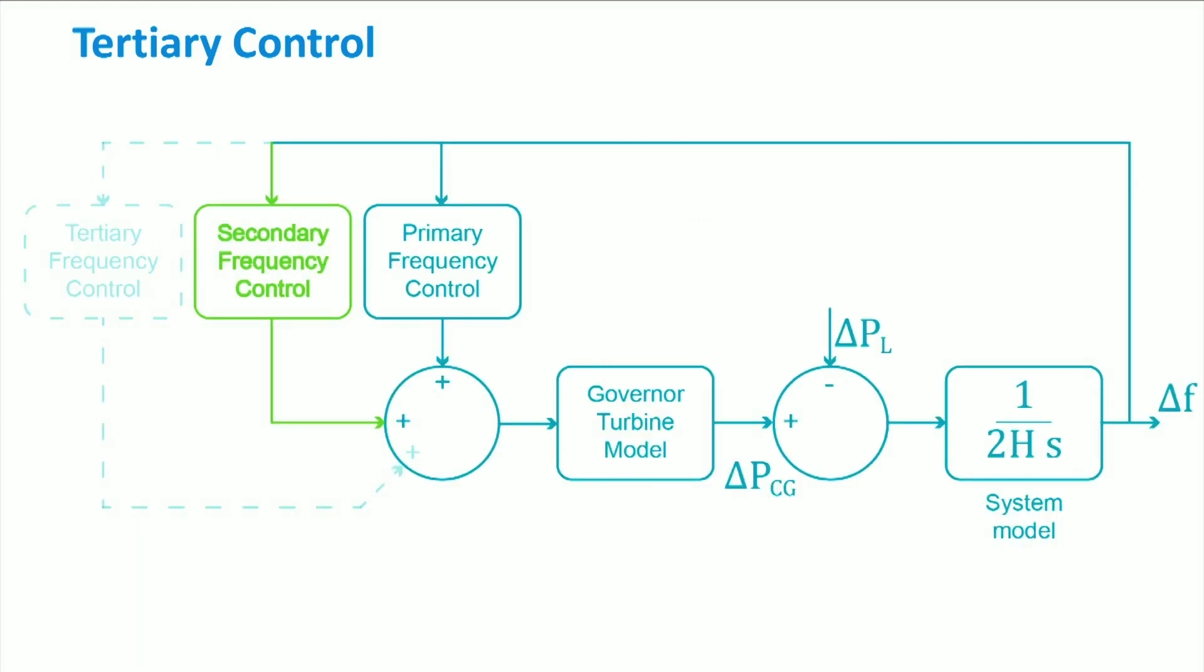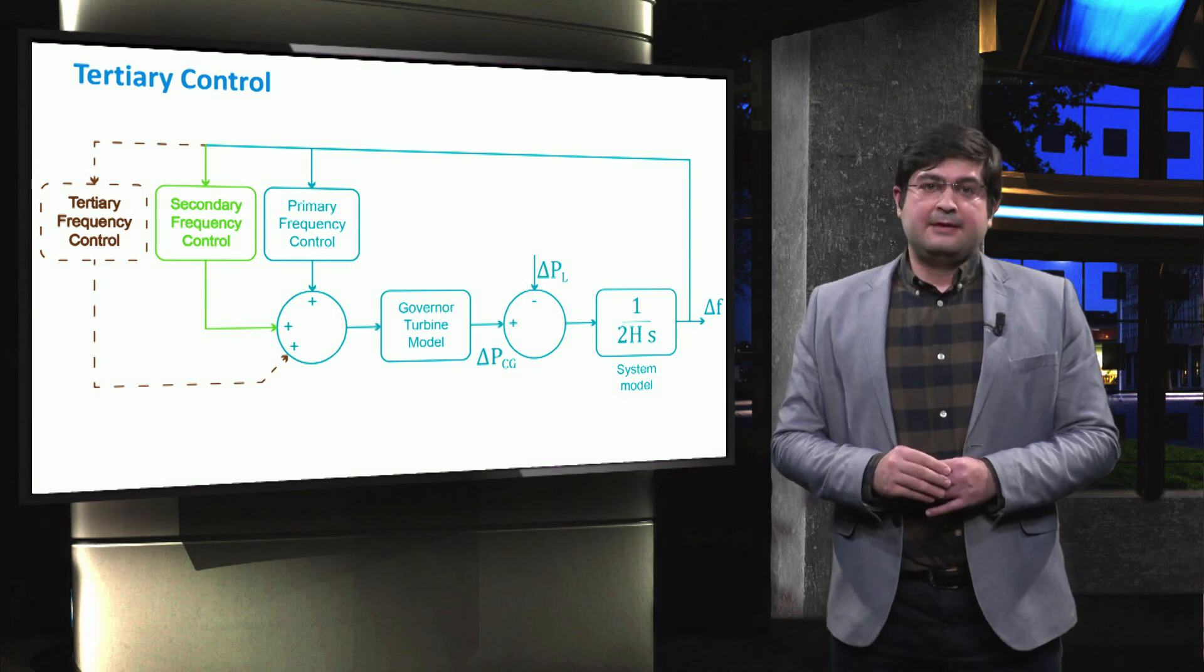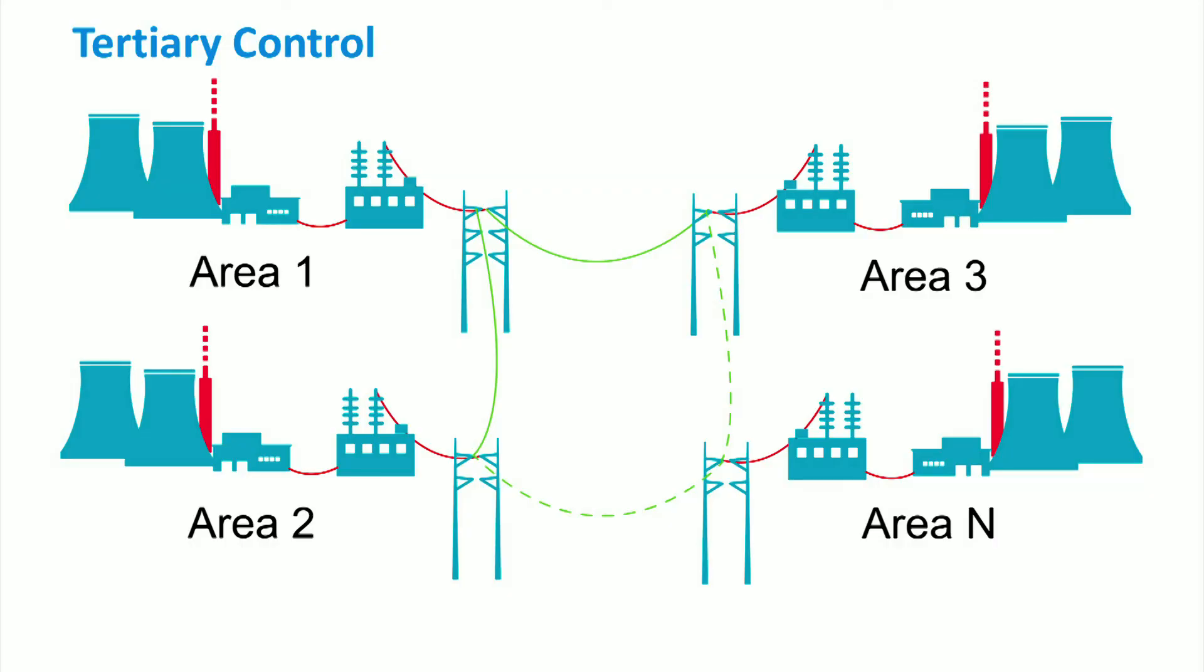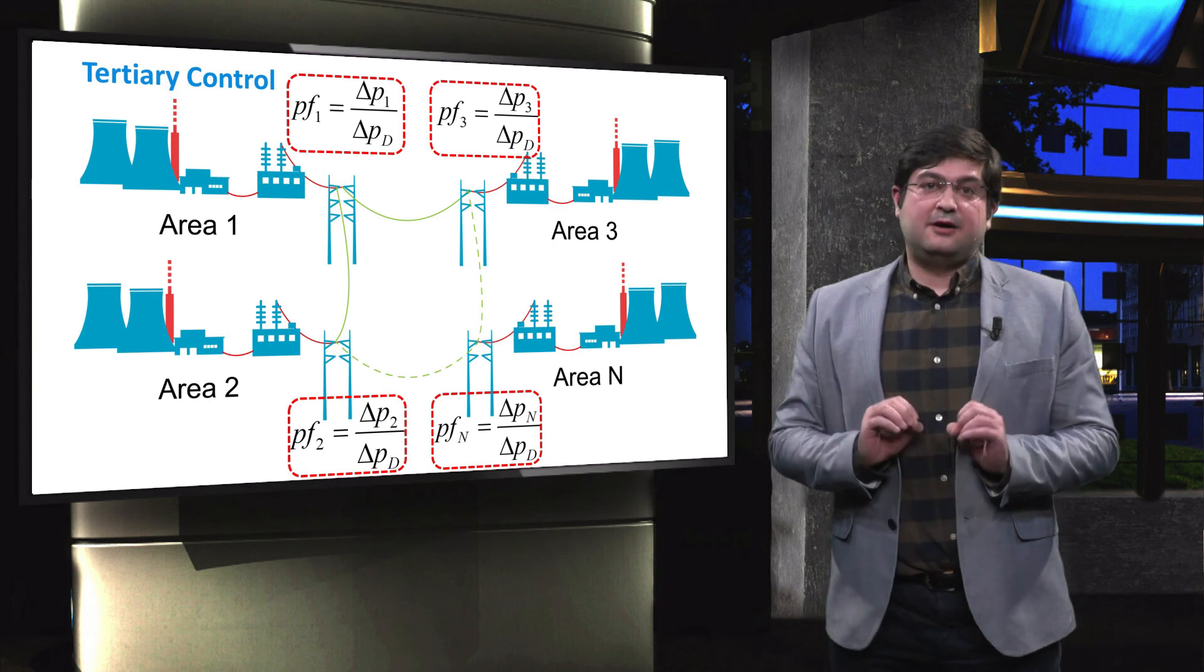The tertiary control is added to the previous control scheme where it manually adjusts the persistent deviation of the power from several minutes to several hours after the disturbance. In multi-area electrical grids, for instance from area 1 to area n, the area control error shall be properly distributed among all the generators and this is why the tertiary control is needed. This is typically carried out through a factor, the so-called participation factor, PF. Note that these participation factors for the areas 1 to n are determined according to the outcomes of the economic dispatch.